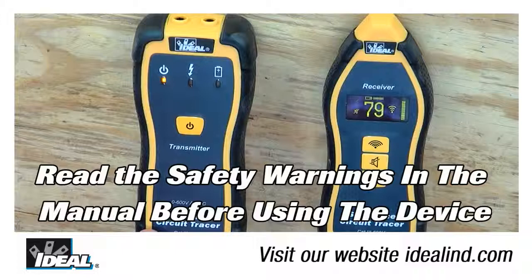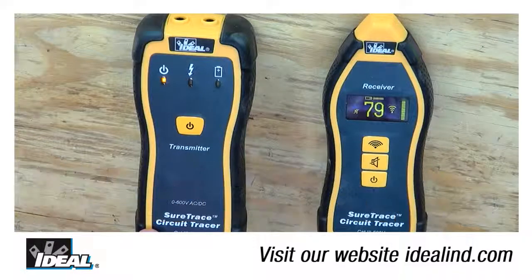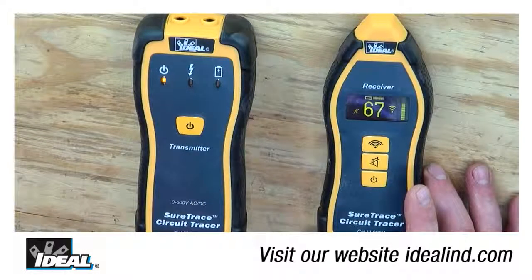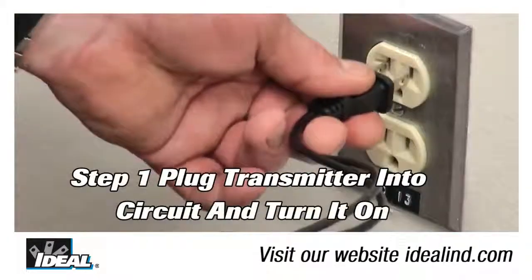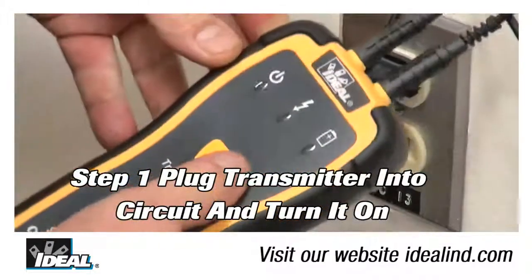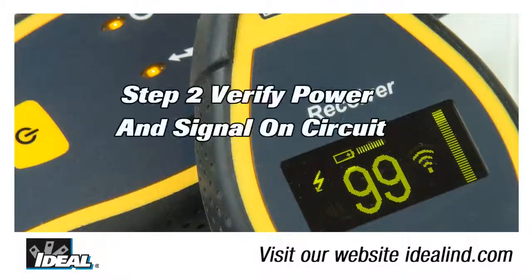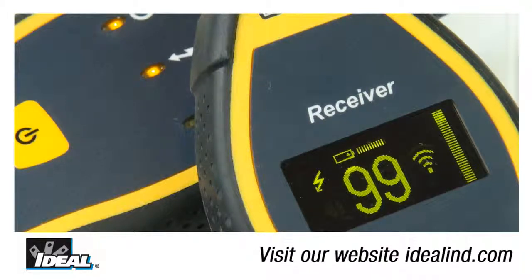The transmitter produces a unique signal onto the circuit to be traced. The receiver provides a numeric value and a variable pitch tone that increases as the signal becomes stronger. Step 1 is to plug the transmitter into the circuit being traced. Step 2, holding the receiver near the transmitter, shows it is receiving a signal, and the lightning bolt symbol indicates power is present on the circuit.